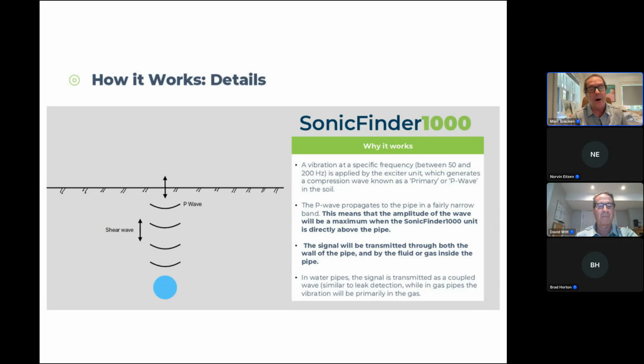In the case of water, it's the same type of wave we use for leak detection, where it's a combined wave between the wall of the pipe and the water. In the case of gas pipe, the wave travels primarily through the gas inside the pipe to the sensor.